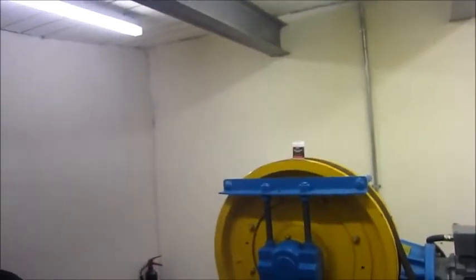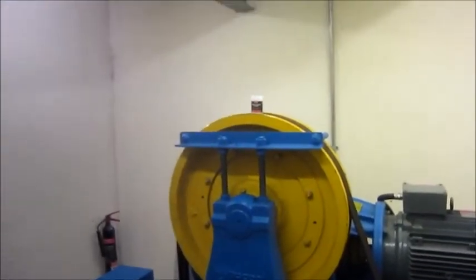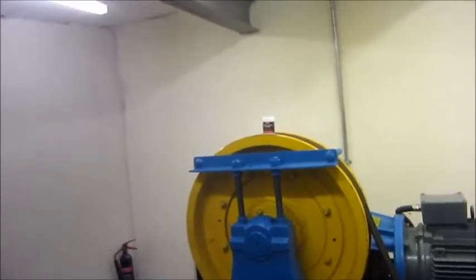If it's underloaded, you prevent it with clever tricks in the software, and load weighing is one thing as well. The high-speed lift has got load weighing on it, so it measures the weight of the car, feeds that back to the control system, and then it knows how much current to apply to the motor to hold, lift the brake, and move away. They're always trying to improve the ride quality, and that's what they compete on: features and functionality of the control system, but also ride quality.